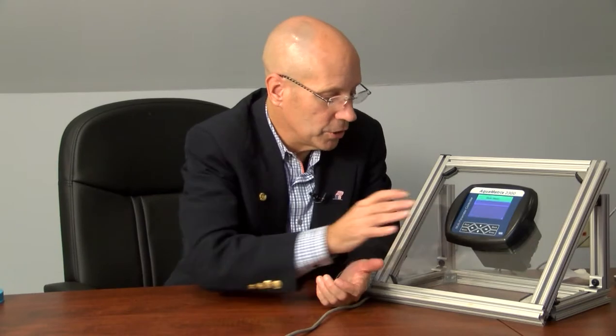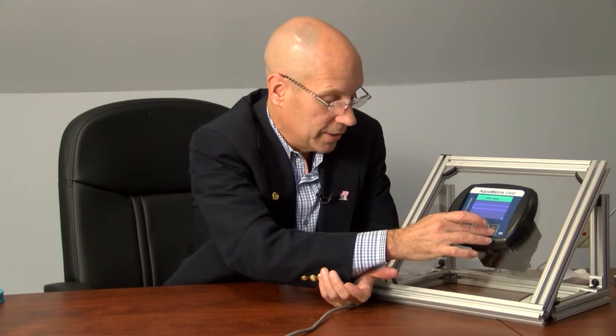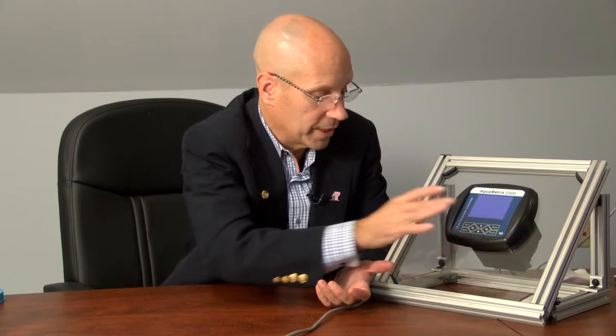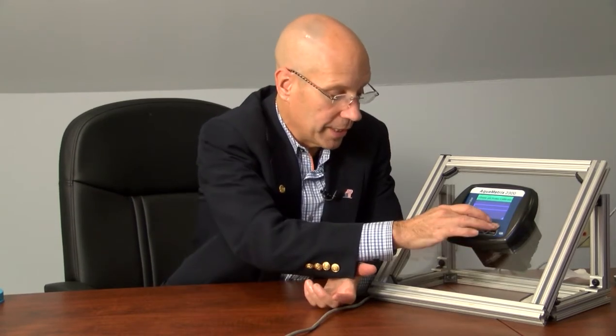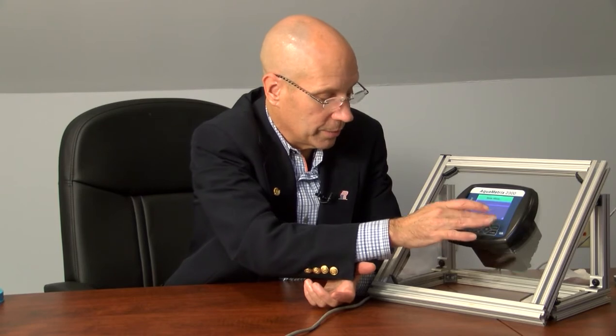Now let's hit the menu button one more time. The next menu item is Calibrate/Disable Probe. This allows me to do a calibration on the system without using a computer or smart device. If I choose that option, all I have to do is follow the on-screen instructions to perform the calibrations. I can only perform 2-point calibrations using the front panel control. It's all self-explanatory. Let's go back. Let's see what the other item is.